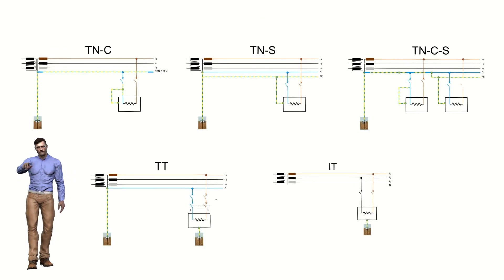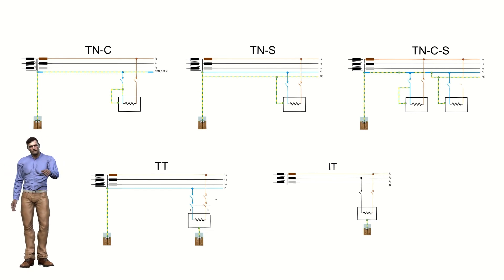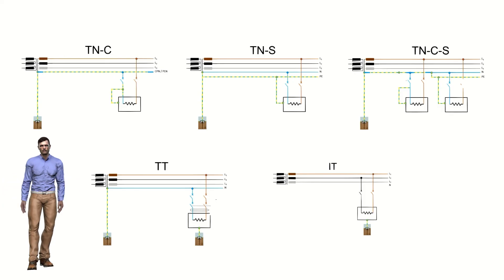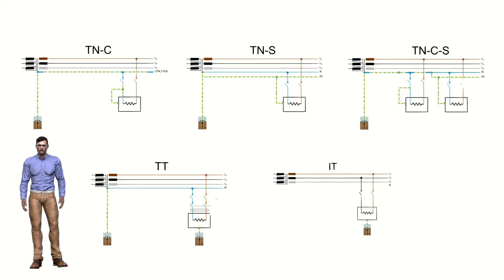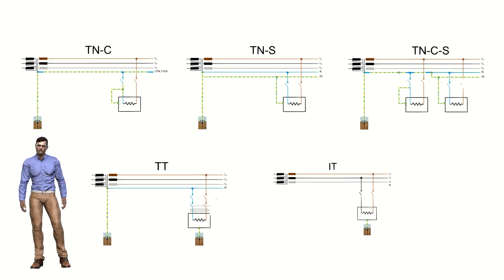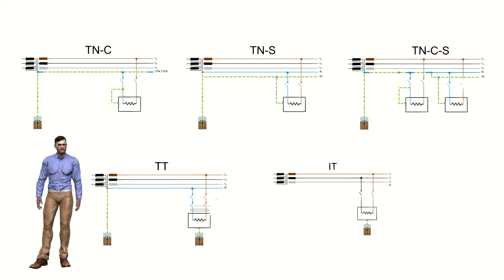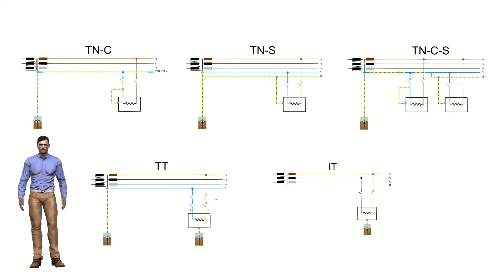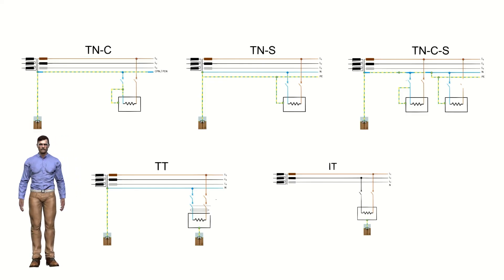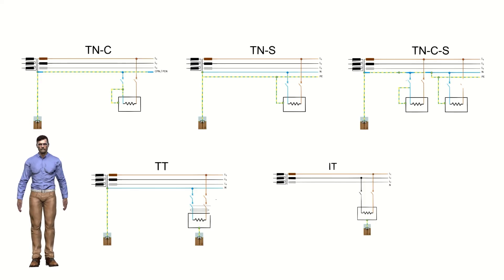Each distribution scheme has its advantages and disadvantages. The TN system implies a lower cost in electrical protections but requires an adequate selection of protections and offers lower protection against fire. The TT system offers high protection of people, of the installation's own loads, and against fires, but requires greater surveillance of the grounds and verification of the correct operation of the differential protections. The IT system has the advantage of offering high availability and fire protection, but installations cannot be too extensive and usually require insulation monitoring devices.